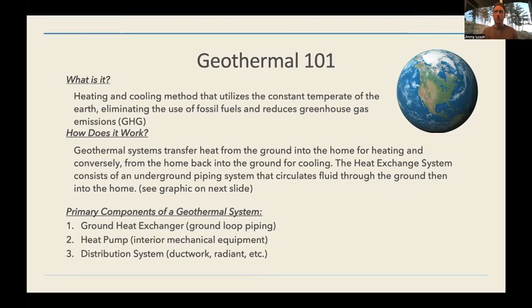There are 3 primary components of a geothermal system: the ground heat exchanger, which is your ground loop, as we may call it, or underground series of piping. On the inside, you will find a heat pump. This would be very similar to the size or look of a gas furnace or maybe an air source heat pump, which sits outside, but that is your interior mechanical equipment. And then from there, you have your distribution system as you would in any typical home, whether that's forced air ductwork, hydronic heating through radiant in-floor, or fan coils of that sort.